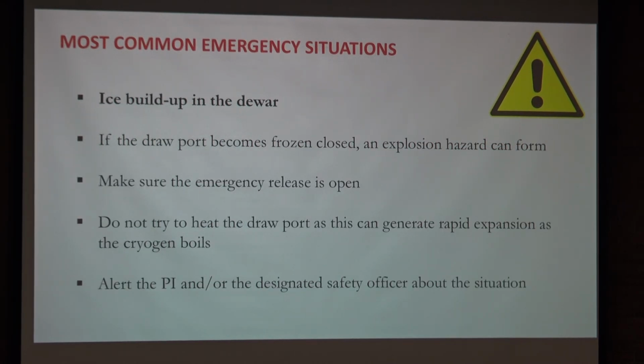Ice buildup in the dewar. If the draw port becomes frozen, then there could be an explosion hazard. Make sure that the emergency relief valves remain open. Don't try to heat it up yourself with a hot air gun. Some people want to use metallic rods with a hot air gun to actually melt through the blockage.